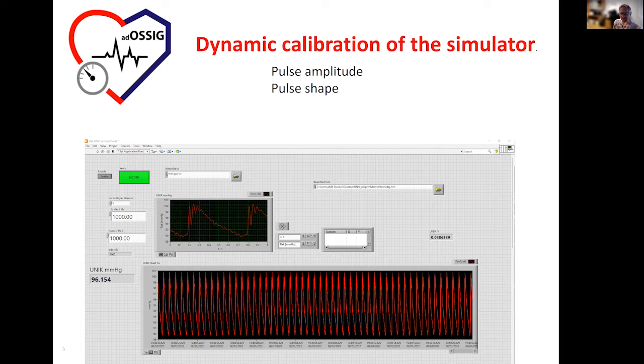This is now the front panel of one of the instruments when we were testing the simulator. The simulator was set, so it was plugged to 96 millimeters of mercury static pressure, meaning that according to the 96 millimeters of mercury, the simulator would pick a certain physiological signal and then use the shape, the form and the amplitude of these pressure pulses according to this 96 millimeters of mercury.